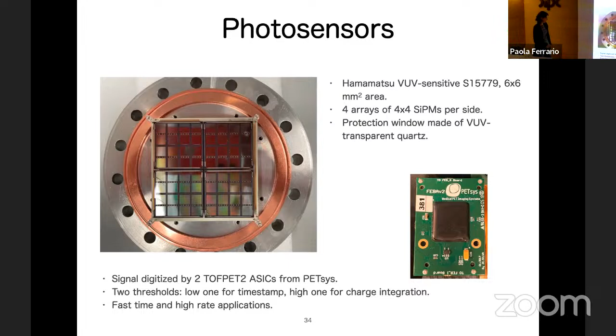We digitize the signal of the silicon PMs with 2 ASICs from the PETSys company, which are here. They are designed specifically for this kind of application. They have 2 thresholds: a very low one that gives you the timestamp of the event for time resolution, and a higher one that allows you to integrate the charge and gives you the energy measurement. And as I said, they were designed specifically for PET systems.